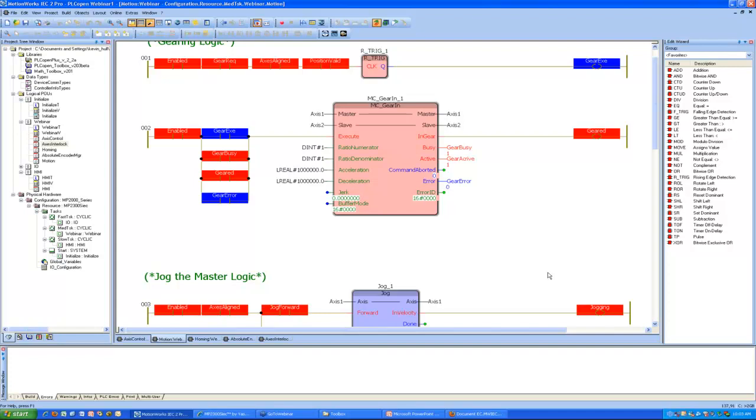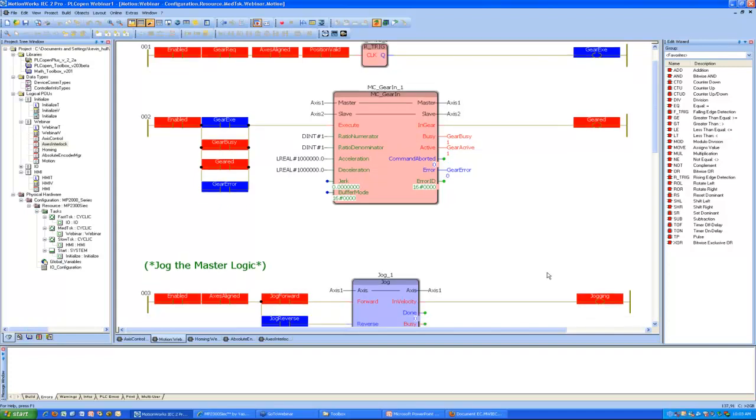So in the case of a gantry, that's basically set for linear mode typically, where the axes are captivated on slides, maybe run by a ball screw. But we've had a number of other applications that would be rotary mode as well, that have two motors that share the same load. And so this function block will work for those applications as well.